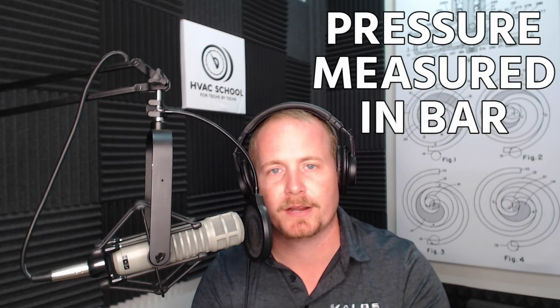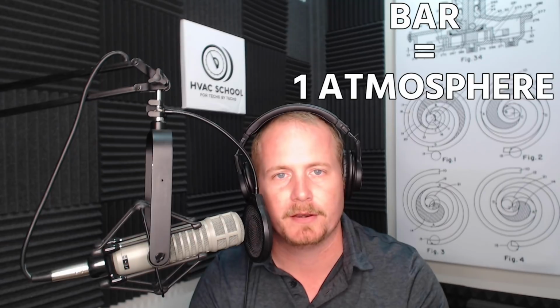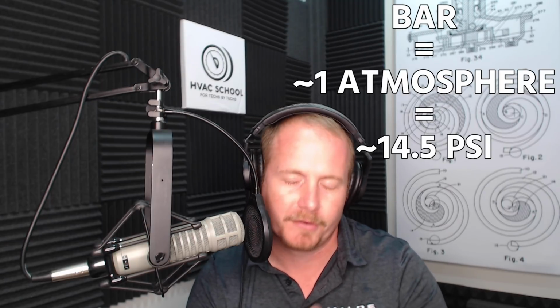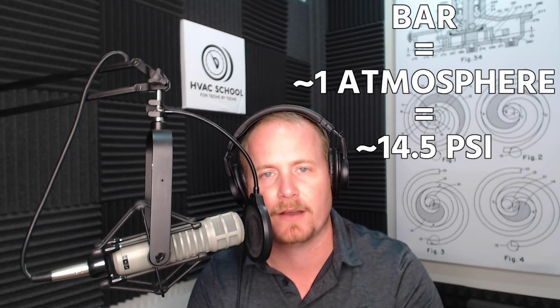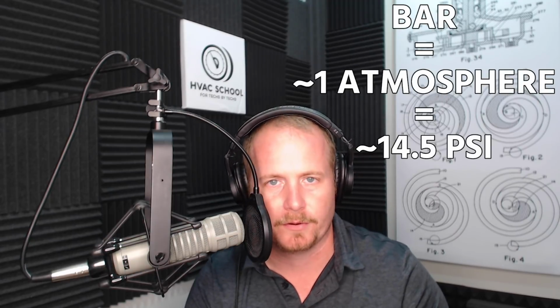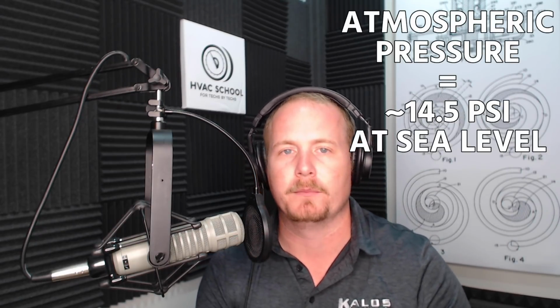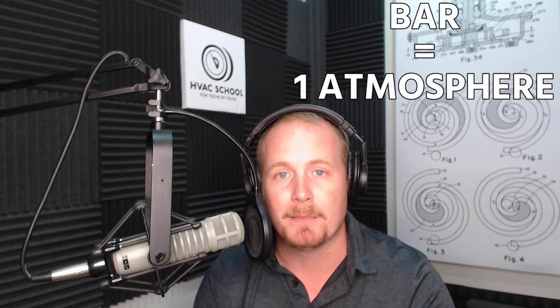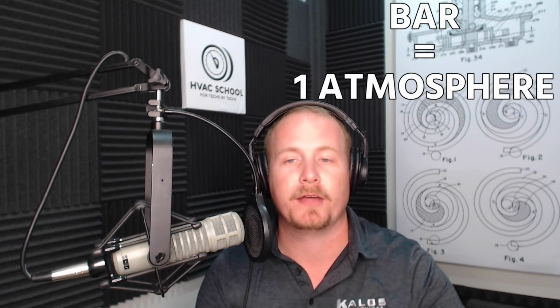But again, it all comes down to the saturation temperature of that refrigerant. Another thing you see a lot with CO2 is the pressure measured in bar. Bar is a European pressure standard that's used quite often, and a bar is 1 atmosphere or very close to it. It's approximately 14.5 PSI. As you know, atmospheric pressure is 14.7 PSIA at sea level, and that's where they get that 14.5 from. So 1 bar equals 1 atmosphere of pressure, so 2 bar would be double that, and so on and so forth.